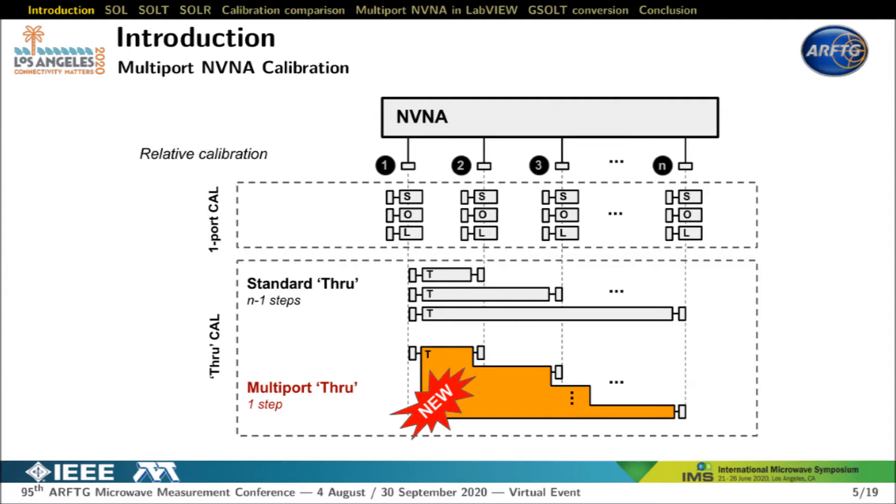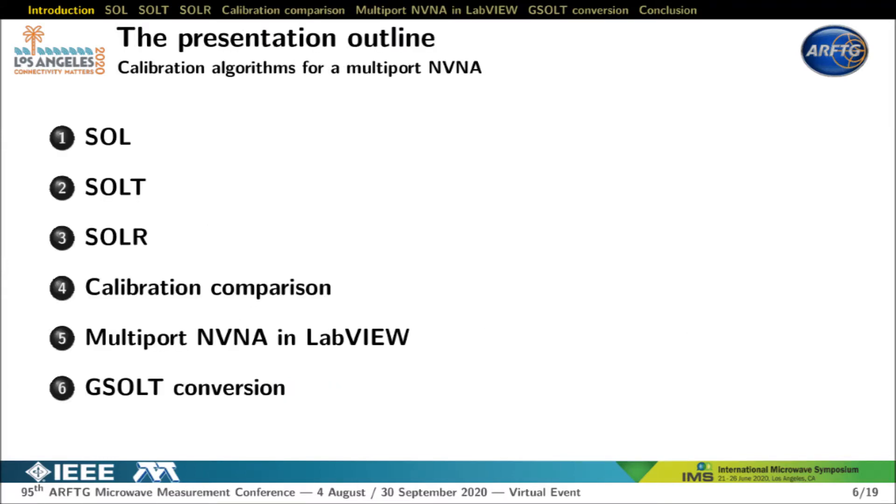This paper presents the theory and application of using a multi-port through in order to calibrate an NVNA with a large number of ports in one shot. First, I will remind you what a one-port short open load calibration is and how we get three error terms per port on an NVNA. Then I will present the SOLT calibration method, where we assume perfect knowledge of the S-parameters of the through standard. By applying an excitation signal on port 1 only, we measure every port simultaneously and can identify all transmission error terms on a multi-port NVNA in one shot.